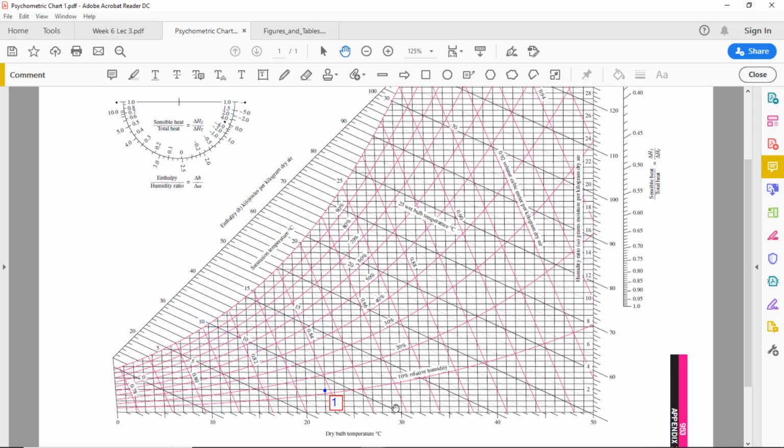And the humidity ratio, you can see we are just under 2 grams per kilogram dry air, so that was 1.9 gram per kilogram dry air, and the constant specific enthalpy lines we can draw any one from over here, and if I just take it to the desired state point, you can see this is 20, so this is 22, 24, 26, and this is 27 kilojoules per kilogram dry air.